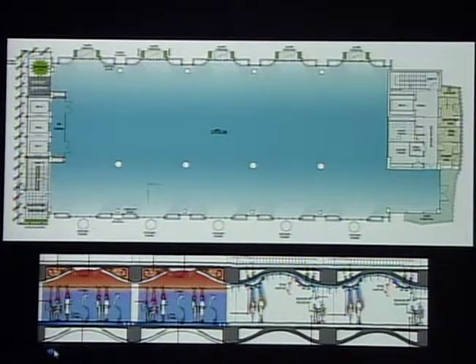Underneath you get this wavy slab, an exposed concrete ceiling, and below it, on the right hand of the section, you'll see chilled panels made of aluminium with cold water circulating in them. The whole idea is radiant cooling, not cooling with air. The air is not recycled, it's 100% fresh air all the time, so it simply passes through. You're delivering the air at 20 degrees, sometimes we cool a little with air, but we're trying to avoid that and keep cooling by radiance.